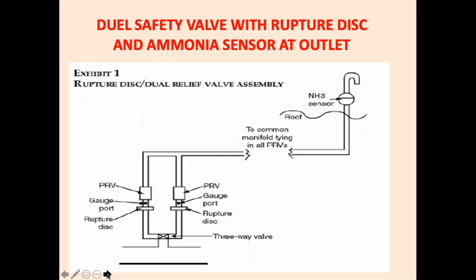These are dual safety valves with a rupture disc and ammonia sensor. Some people also put ammonia sensors, in a very critical plant, at the outlet, and that ammonia sensor will give an alarm indicating that the safety valve has blown off. Otherwise, many times during night time there is no operator and some accident has taken place, people do not know about it. So this is important.